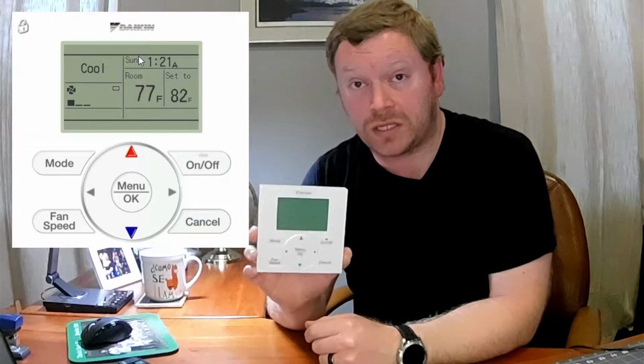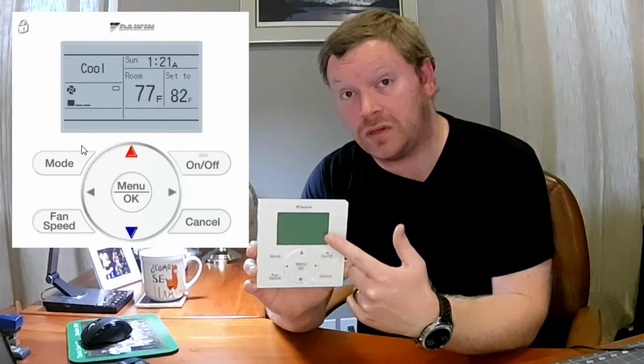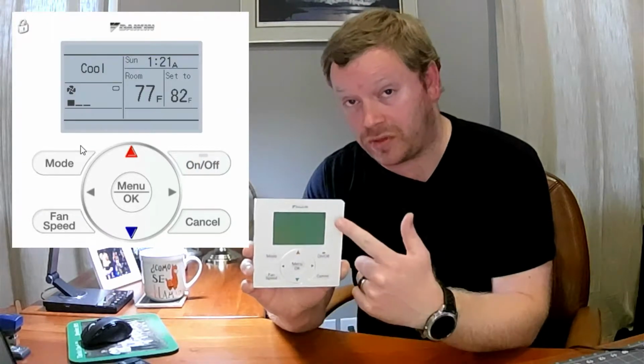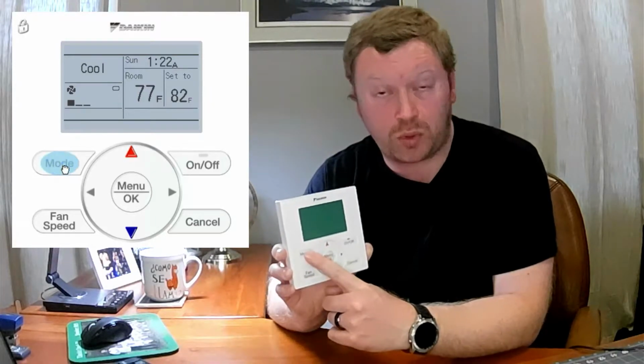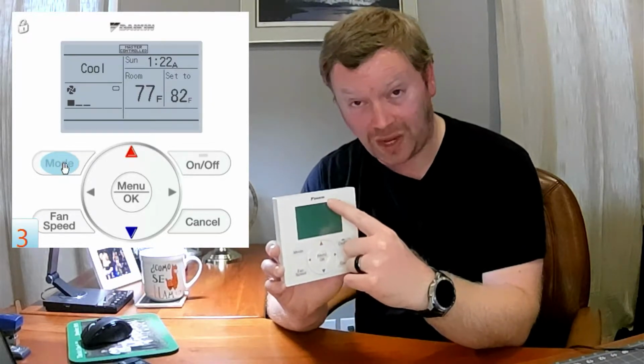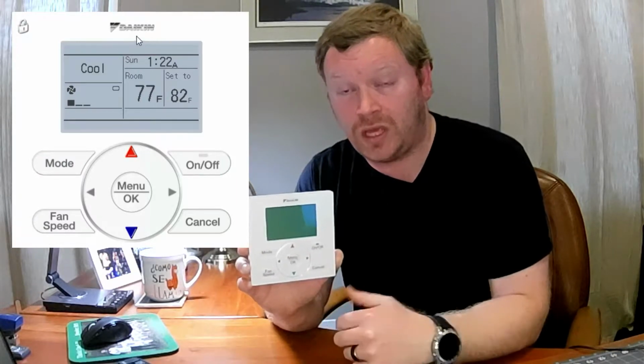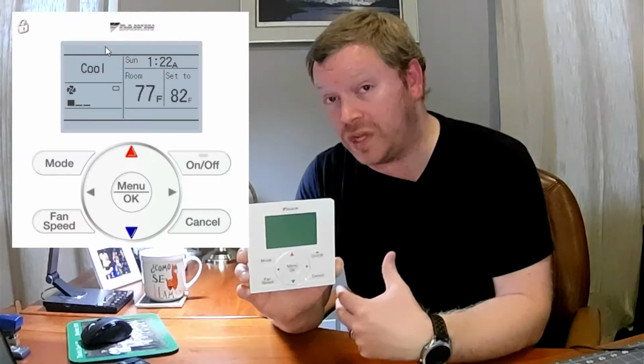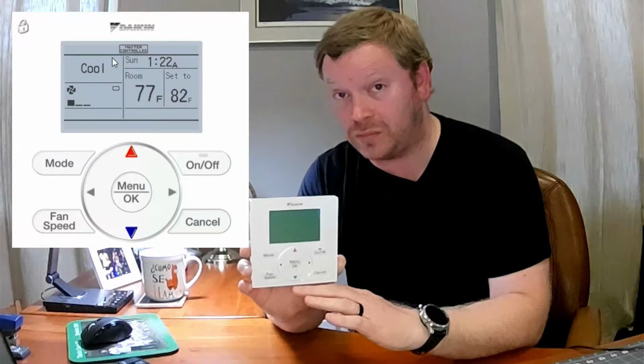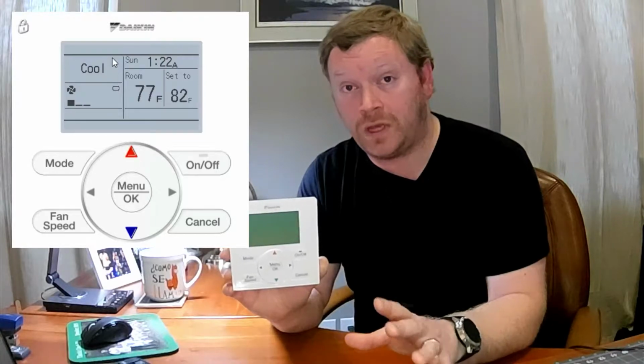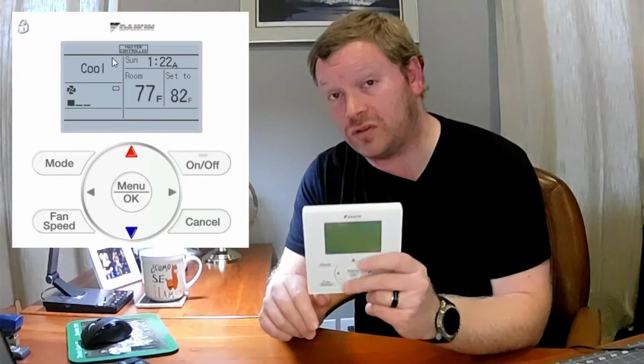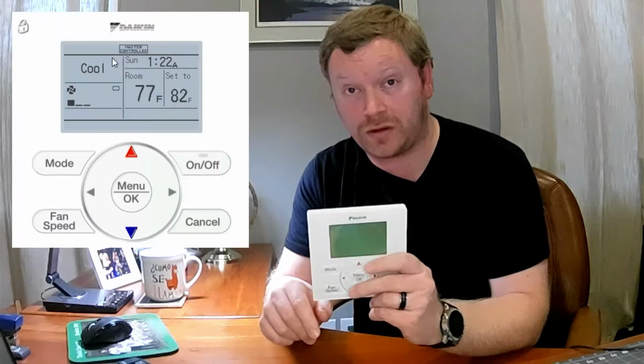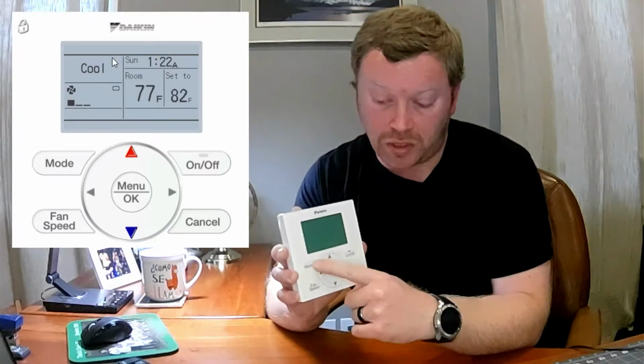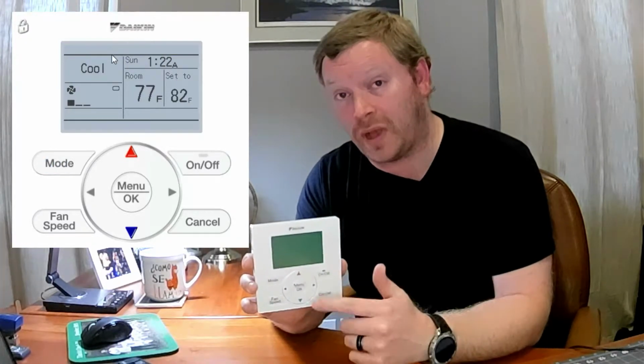Once you've located the master controller, you're going to press any button to illuminate that backlight. Remember, the backlight has to be on before we actually press any buttons. With the backlight illuminated, now all you have to do is press and hold the mode button until master controlled starts blinking at the top. And what you've done now is you have reset which NAV controller is the master. Because right now, with all of them blinking, none of them are the master. With them blinking, now walk over to the NAV controller that you do want set up as the master. Simply illuminate the backlight, and then all you have to do is press the mode button one time, and bada bing, bada boom, now you've moved your master controller.